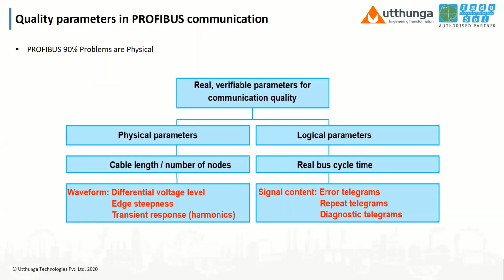Coming to quality parameters in Profibus communication. What are the relevant quality parameters? In Profibus communication, we have found that physical problems are 90% of the issues in the network. Physical problems such as cable length or node issues, and also connectors or any cable breaks. 10% of issues are on the logical side, like cycle time issues or any error telegrams, repeat telegrams, diagnostic telegrams. We will take this in detail in the next few slides.